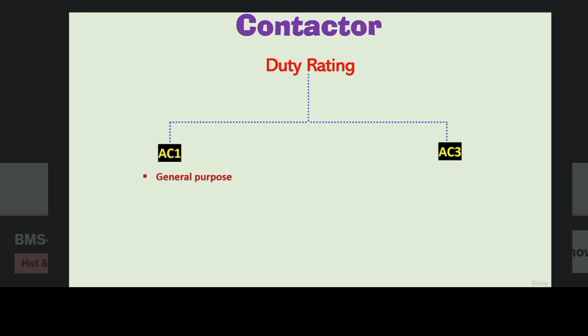Now let's have a brief look at the duty rating of contactors. Contactors have different duty ratings like AC1, AC2, AC3 and AC4 and so on, but we will discuss here only AC1 and AC3 ratings, which are more commonly used in our BMS applications. AC1 are general purpose contactors which are used for non-inductive or slightly inductive loads, for example electric heaters. These loads shall have a power factor between 0.95 and 1.